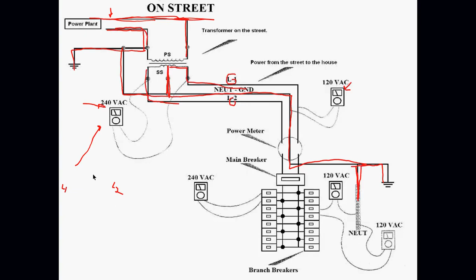In your breaker panel, you have 2 rows of breakers. Depending on which side of the breaker panel that breaker's on, and I'm talking the single pole breakers, where it's a single switch, it's either connected to the L1 or the L2. A good electrician, when they set up your breaker panel, balanced the loads. In other words, you don't want all of your appliances on L2. You don't want all of your lights on L1. So they balance the loads out. So half your kitchen appliances would be on L1, half of them on L2.